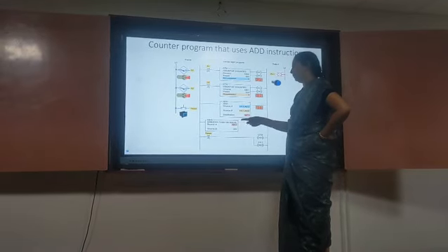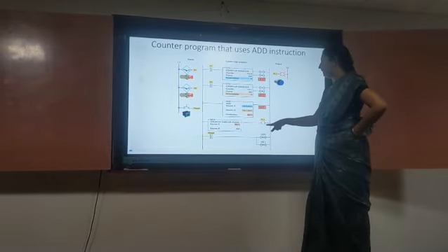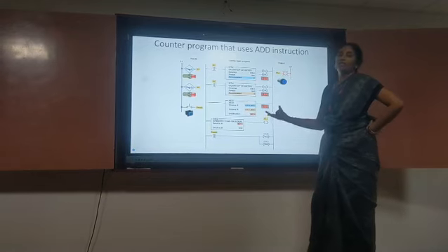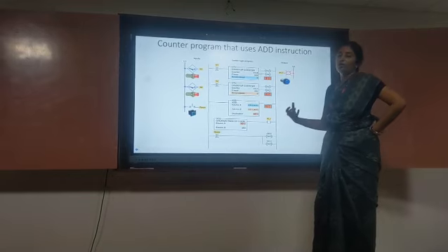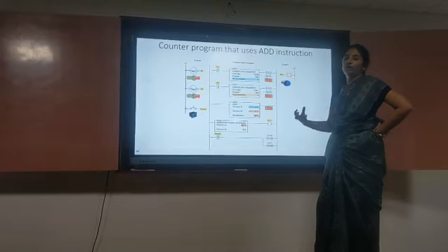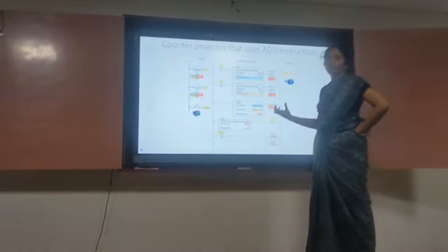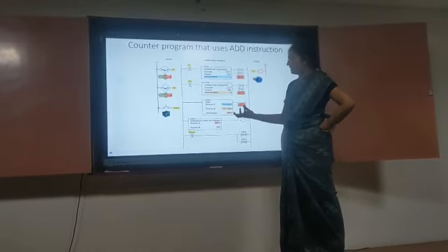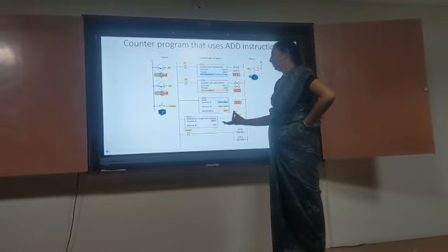So this greater than or equal to block is going to send an output which is going to activate the pilot light. The pilot light is going to glow, which indicates that I have received a number of signals, or a number of components, greater than or equal to 350, which is the required set point. I have set it to 350, maybe I can set it to 400 or whatever is my requirement. Now the pilot light is glowing, which is my requirement.